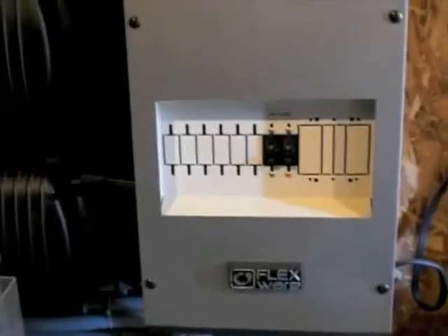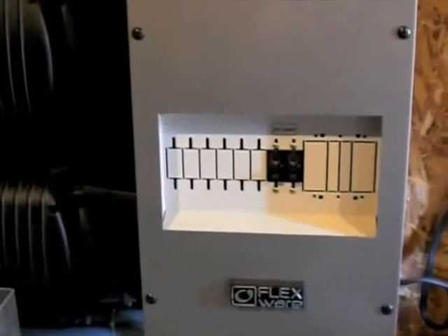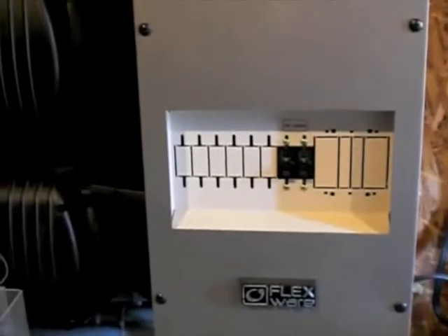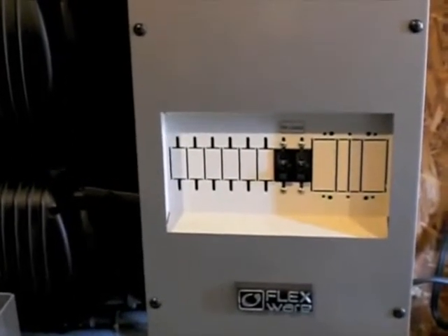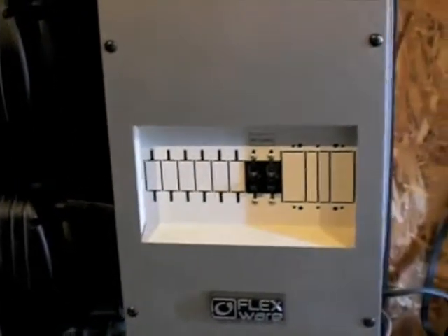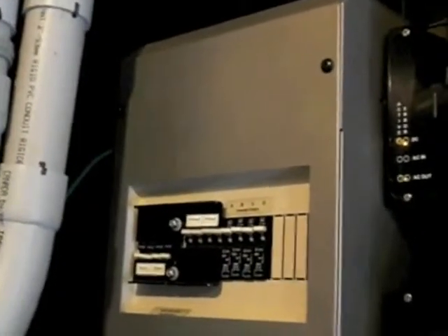On the bottom, we aren't doing it right now, but we have the ability to draw 80 amps of 48 volt power from the unit if we had 48 volt loads, but there's no need for that at this location. On the left side of the FlexWare we have a series of breakers at the top, and these protect the input and the output of the AC activity on this inverter system.